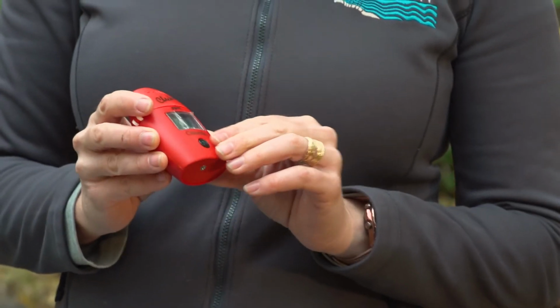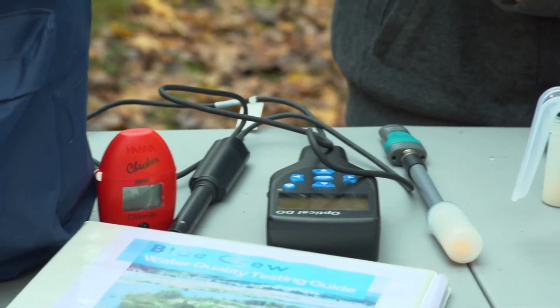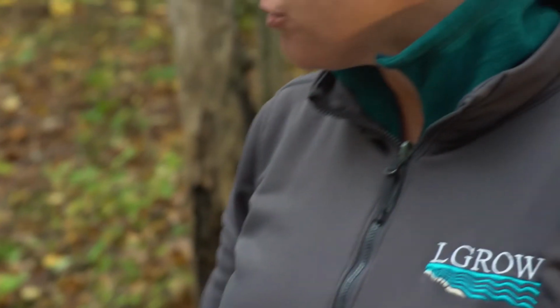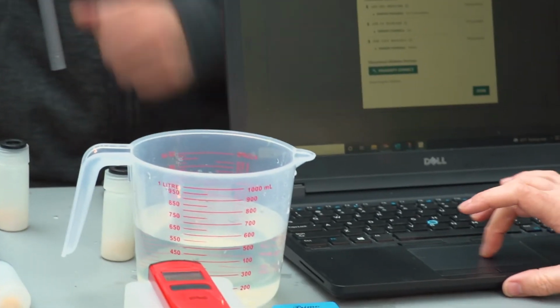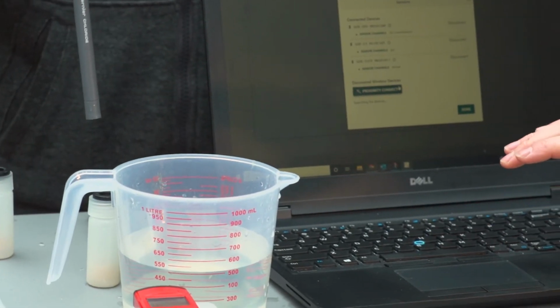This one functions a lot like the phosphate checker we looked at earlier, so I'm not going to demonstrate it, but know that if your result is blinking at the end, that means it was out of range and your level is above 20 parts per million. This is a situation where it'd be great to have the chloride probe, because it gives us a much better range of chloride in your system.